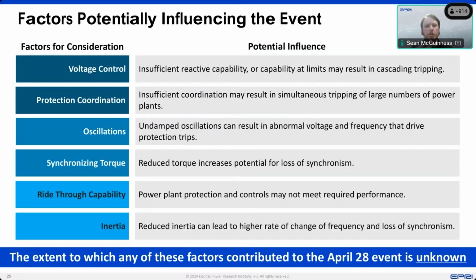So recognizing how well synchronous generators are tied together on your grid is in many ways as important or more important than simply looking at inertia itself for how fast frequency will change in the grid, but how fast can the grid actually lose synchronism or split apart.